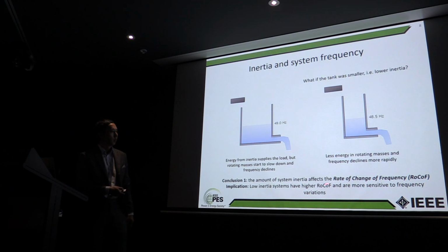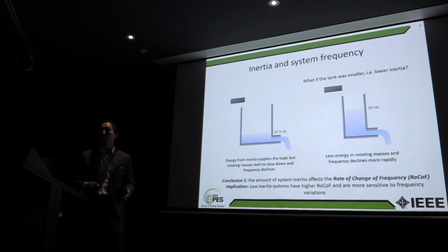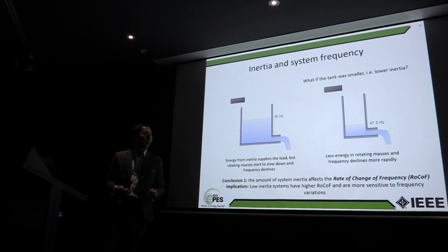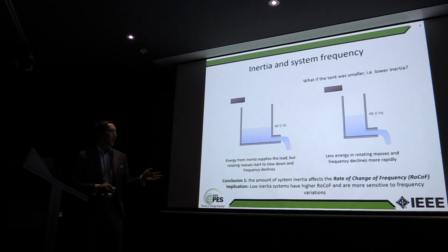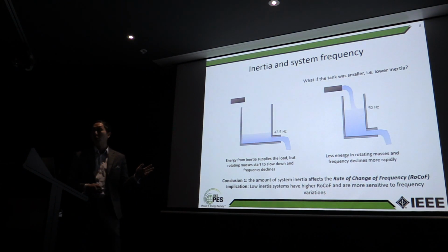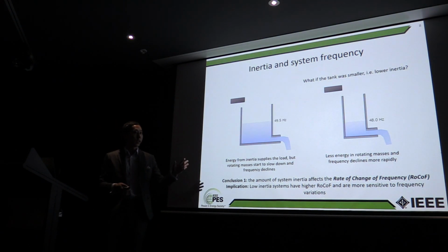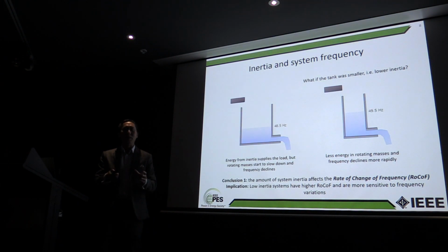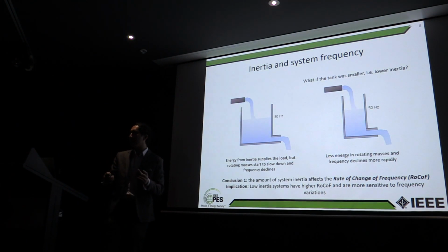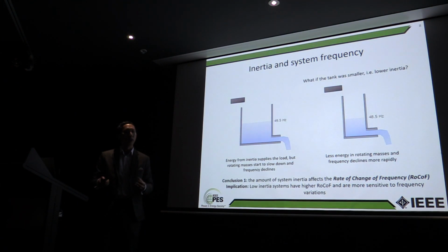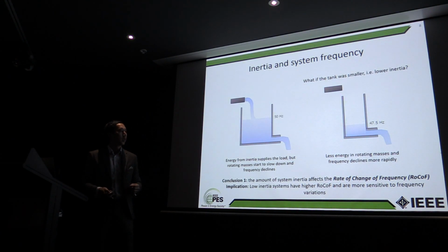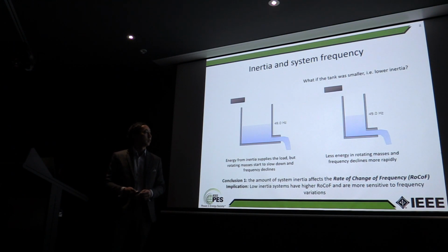That's an important term that we often use, we say ROCOF. And the implication is that low inertia systems have a higher ROCOF. As a result, small mismatches in generation and load give a more volatile frequency, so it's much more sensitive to frequency variations.